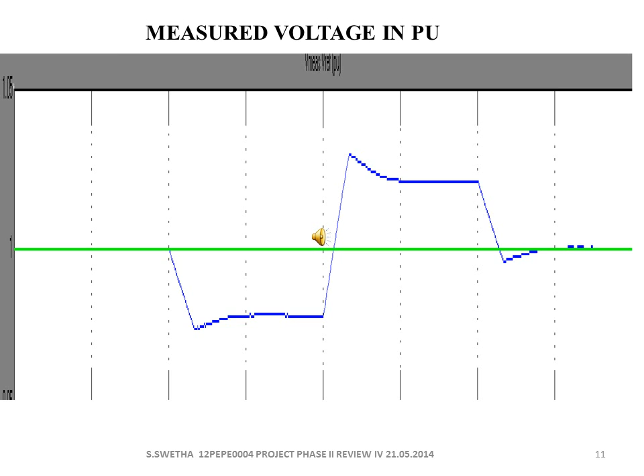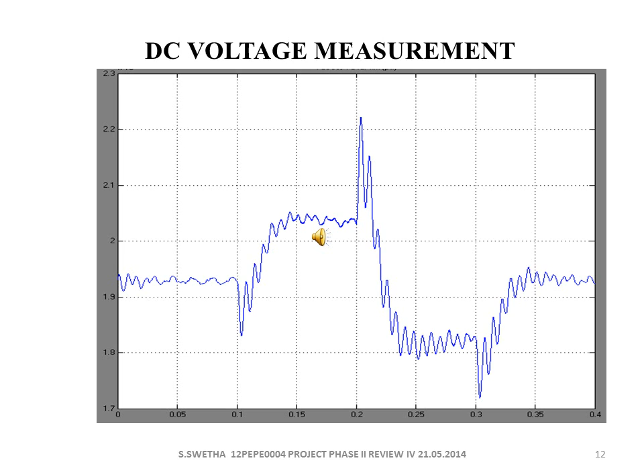This wave shows my measured output voltage in per-unit value. This wave shows the DC voltage measured across the capacitor. The positive wave indicates the charging of the capacitor, while the negative wave indicates the discharging of the capacitor. The main advantages of STATCOM are that it keeps the voltage constant by removing voltage sag and swell. It protects the electrical equipment. Line current is reduced, thereby losses in the transmission lines are reduced.